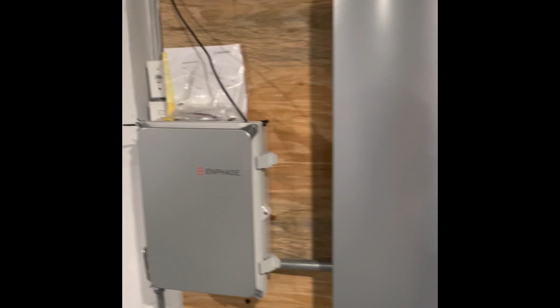So the solar power actually comes in through this combiner box. This is where my breakers are from all the microinverters on my roof. And then it goes to this box first. When the power goes out, this device will sense it and cut off the flow of power to this 90 amp breaker, and it will only allow power to flow from my automatic transfer switch into this secondary critical loads box that includes all of my 120 breakers.